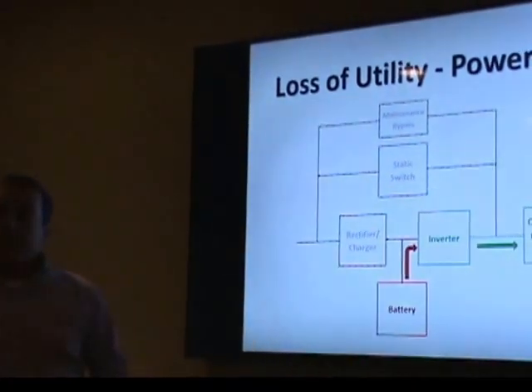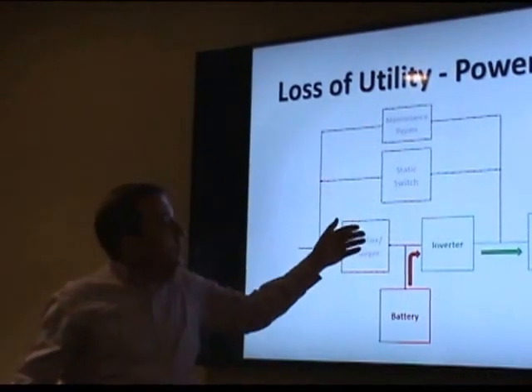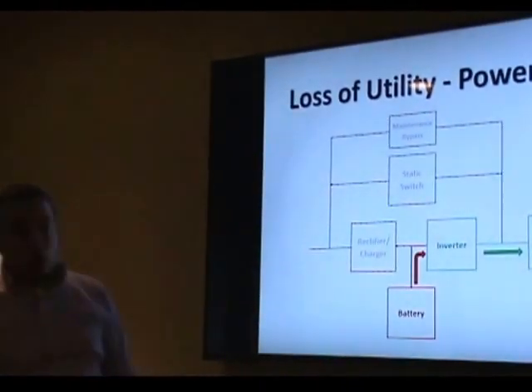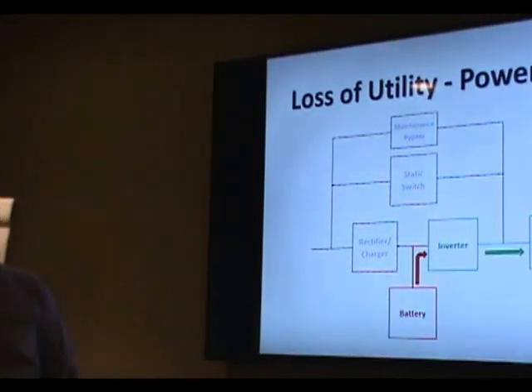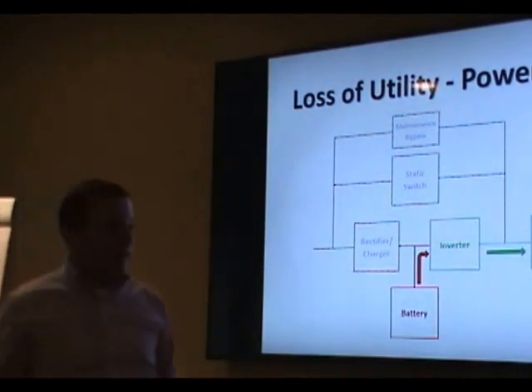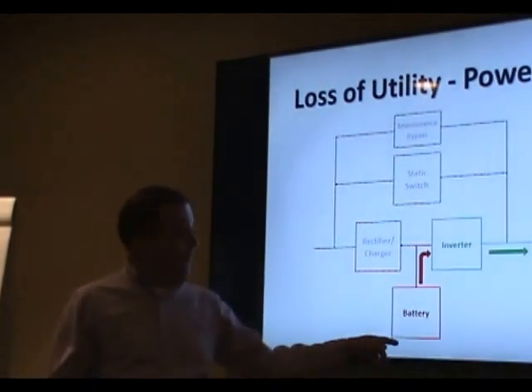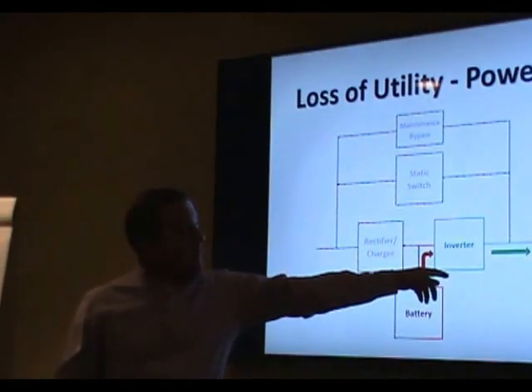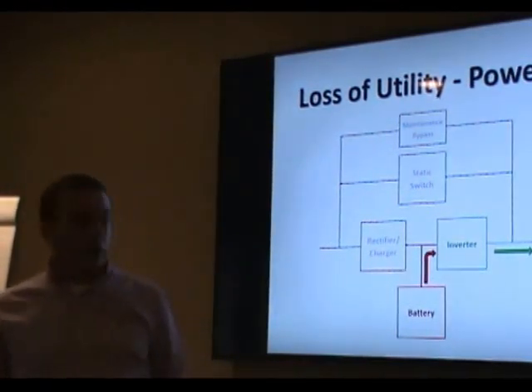In the event that there's a power outage, all these gray boxes here are de-energized, so you have no power going to your rectifier charger, no power going to the static switch, no power going to the maintenance bypass. The only power you have is the battery system. The battery basically feeds the inverter, the inverter makes AC power and pumps it out to the computer load.